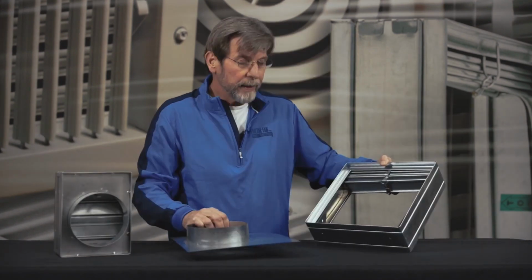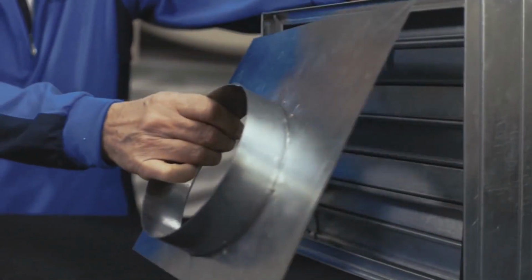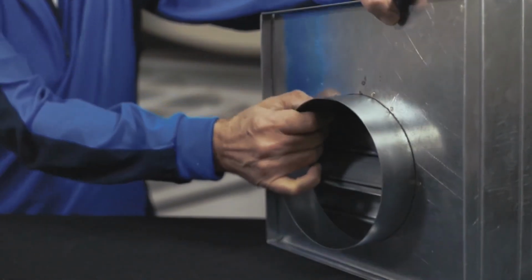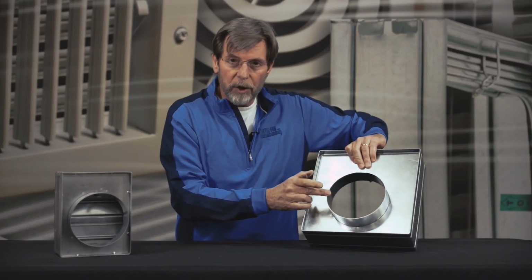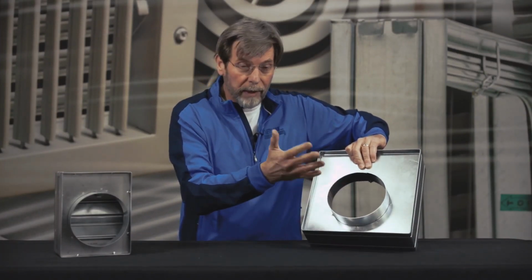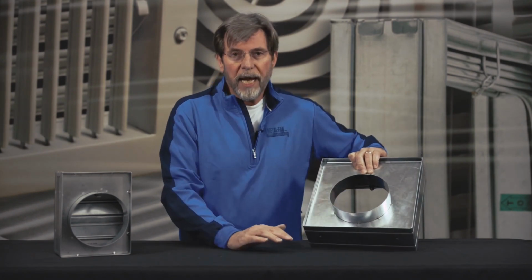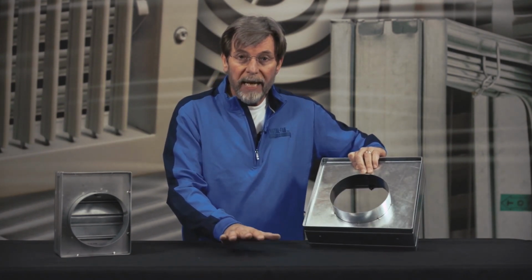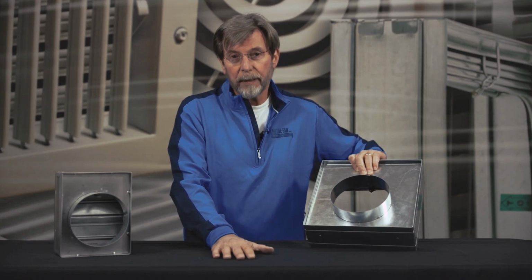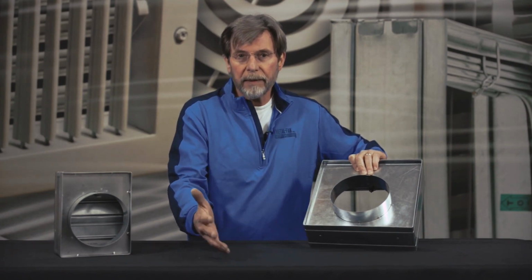And when you order a type C damper, we're going to start with the type A. We're going to add this transition plate I just pointed out. We're going to add a duct transition collar, whether it's round, square, rectangular, or oval. This is going to make it a type C damper. Type C dampers are considered to have 100% free airflow, so they have the best airflow characteristics between the type A, type B, and type C.